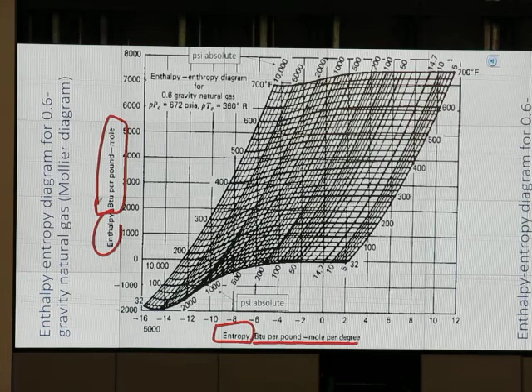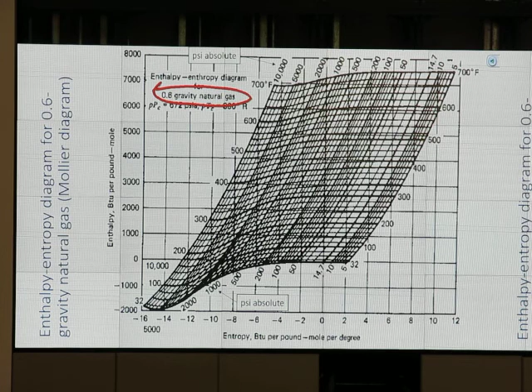The way we use it is the same way. Number one, we need to open the right chart. This is the chart for 0.6 gravity natural gas. If you have 0.8 or 0.7, don't use this chart, but if you have 0.6, use this chart. Once we open the right chart, we have to know that pressure drop across the choke is constant enthalpy, so we have to move just like that, horizontally.